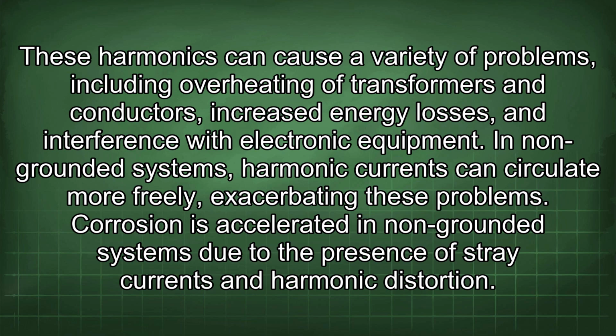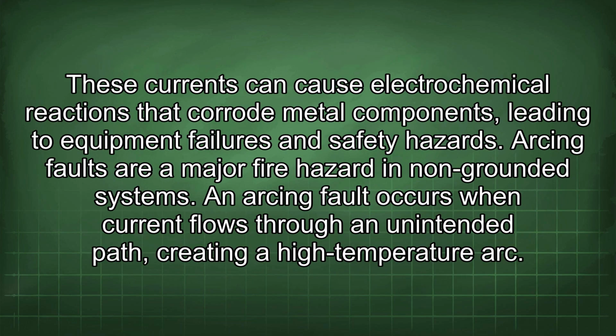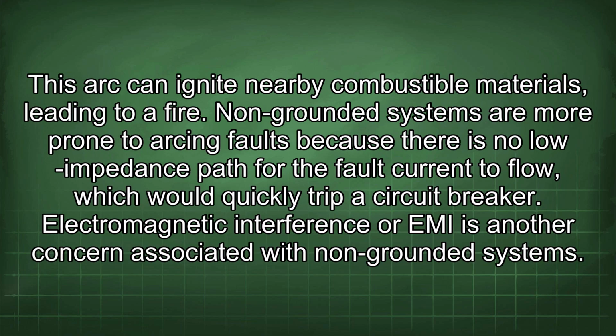Corrosion is accelerated in non-grounded systems due to the presence of stray currents and harmonic distortion. These currents can cause electrochemical reactions that corrode metal components, leading to equipment failures and safety hazards. Arcing faults are a major fire hazard in non-grounded systems. An arcing fault occurs when current flows through an unintended path, creating a high-temperature arc. This arc can ignite nearby combustible materials, leading to a fire.